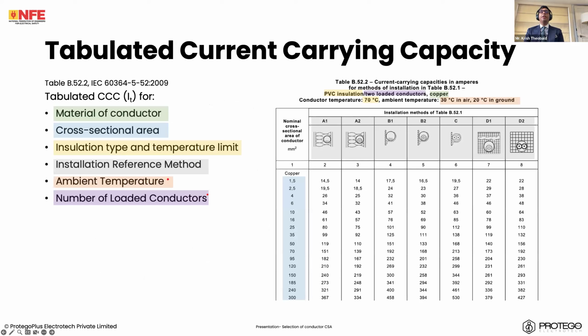See, tabulated current carrying capacities, when you look at our tables, there are a variety of factors to decide what value to choose, and not just what value, what table to choose as well. The material of conductor, so for example, copper in this case, the cross-sectional area, 1.5, 2.5, 4, 6, and so forth. What is the insulation? Is it the PVC insulation? And notice the subsequent temperature limits, 70 degrees.